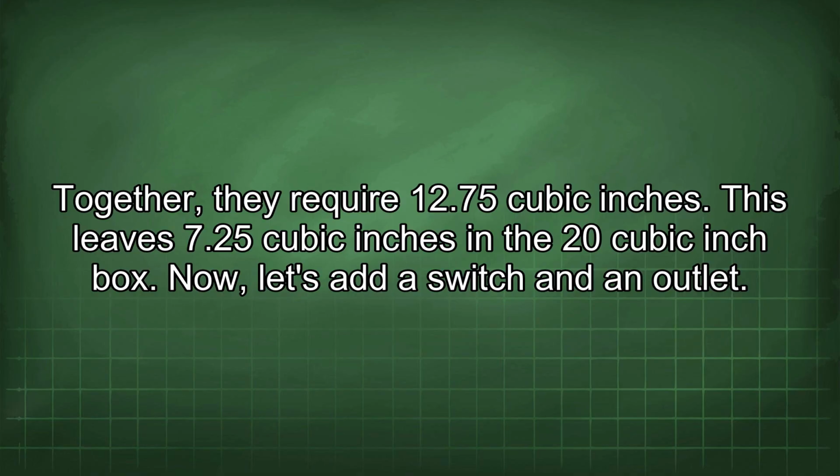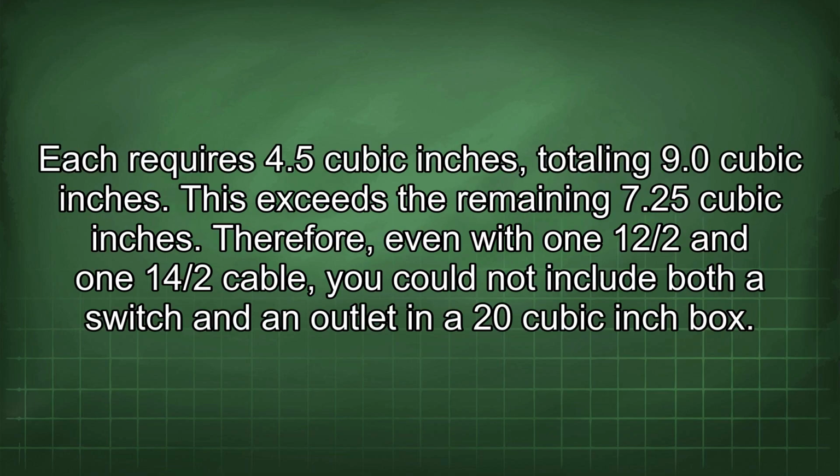Now let's add a switch and an outlet. Each requires 4.5 cubic inches, totaling 9.0 cubic inches. This exceeds the remaining 7.25 cubic inches. Therefore, even with one 12/2 and one 14/2 cable, you could not include both a switch and an outlet in a 20 cubic inch box.